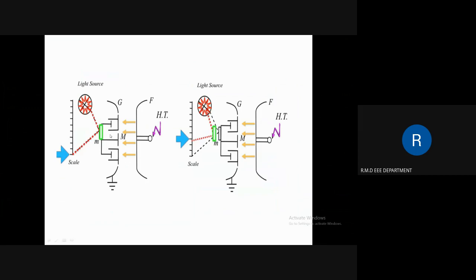Here you can see the principle of operation. When high voltage is applied, there is more force of attraction on the moving electrode and it moves, so the light on the moving electrode is reflected at a particular angle, which is measured using a scale. When the high voltage is increased, there is more force of attraction on the moving electrode, and thus a change in the angle of inclination of the reflected ray, which is observed on the scale. So we are able to measure the high voltage directly with the help of this electrostatic voltmeter.